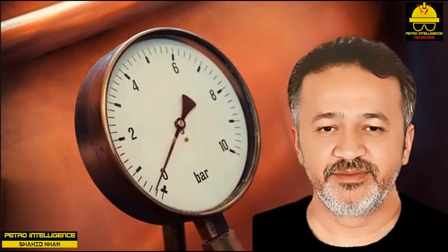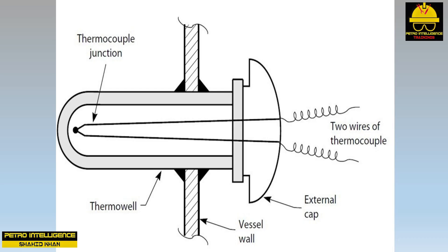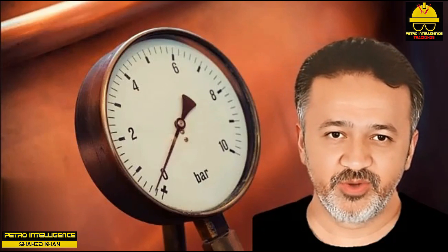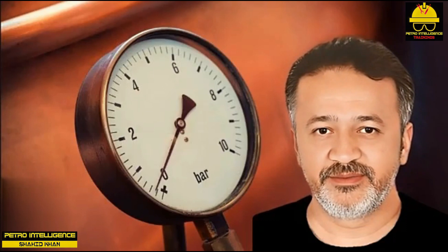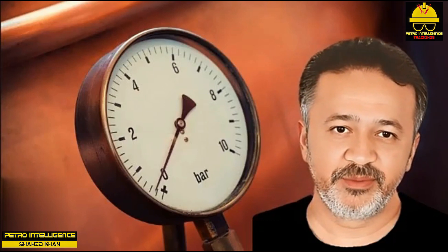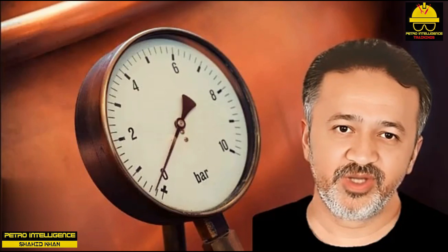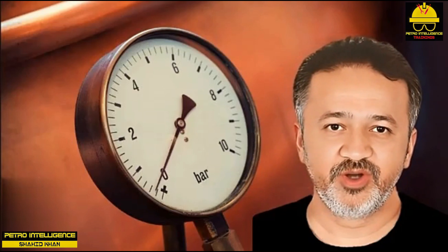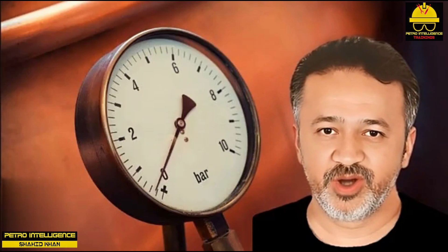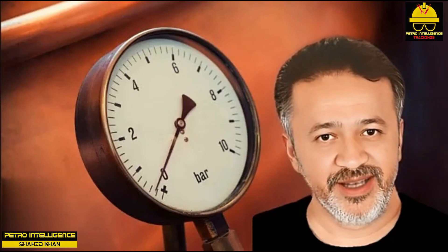Safety note: this picture implies that most thermowells are welded in place, but typically thermowells are screwed into a one-inch nozzle in the vessel wall. Unscrewing a thermocouple is perfectly safe, as is extracting a screwed-in dial thermometer from a thermowell. However, less experienced people have made a deadly error by unscrewing the thermowell itself instead of the thermocouple — unscrewing a thermowell opens the process fluid directly to the atmosphere.